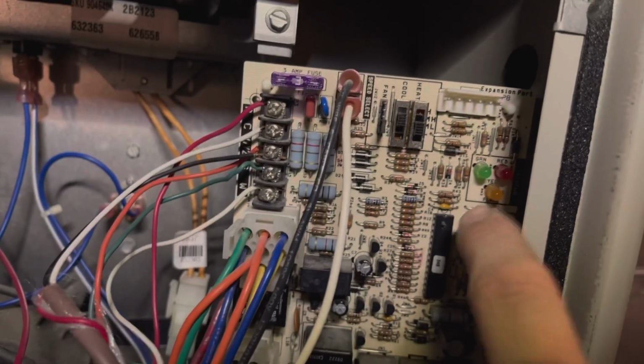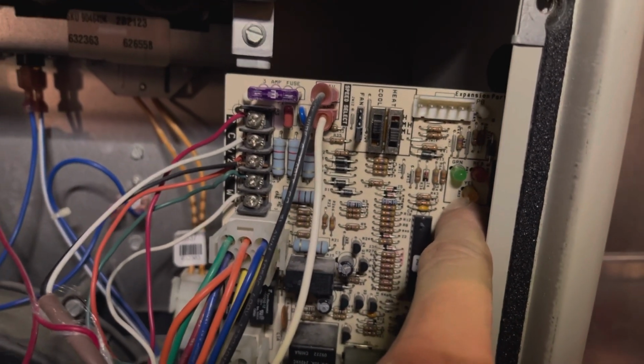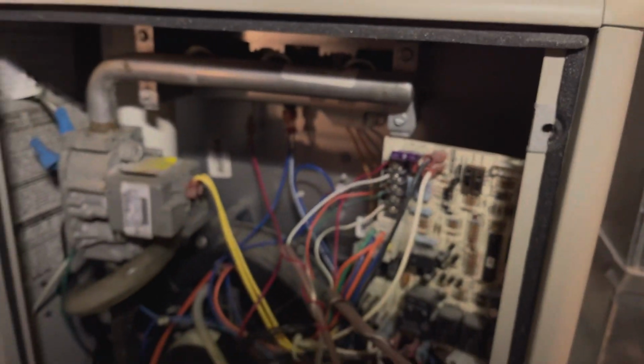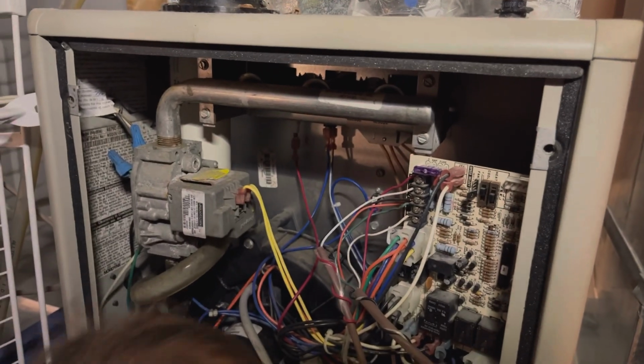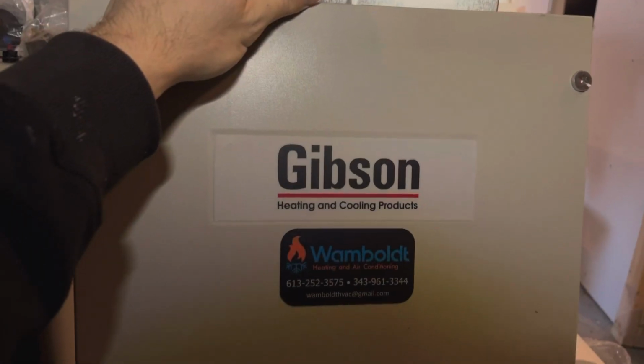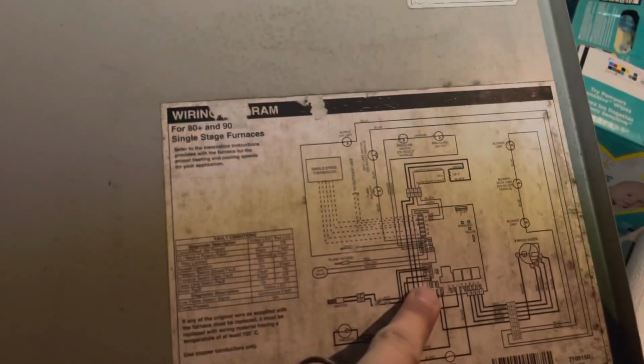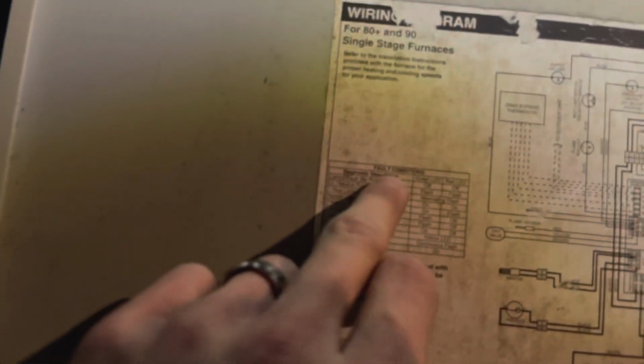Now, when you turn on your furnace, you're going to see these lights, and it'll tell you whether the furnace is running good. If the flame's lit, the yellow light will be lit, or they'll be flashing in a certain sequence. Every furnace is different, and it'll be flashing in a way to tell you what the error code is. On the back of your furnace panel, when you take it off, you'll see a wiring diagram and a fault conditions chart.